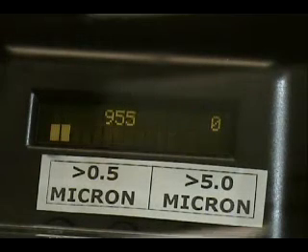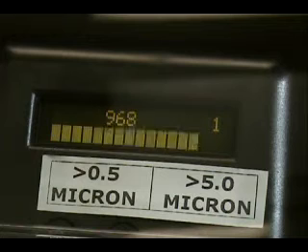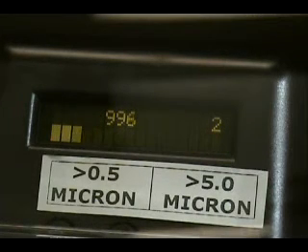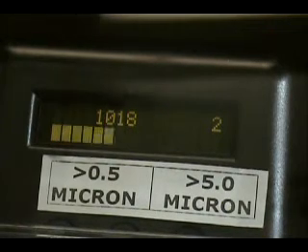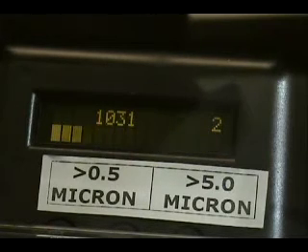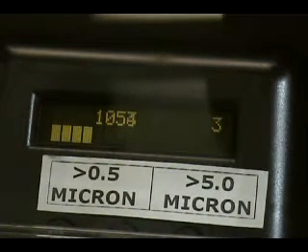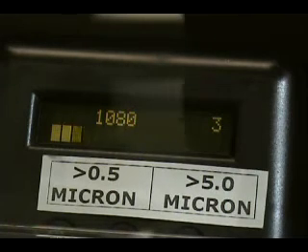I'll take the filter out — particle count will go back up. This is a clean 20 by 20, one-inch air filter. Particle count is going up. The question is, this filter was left in for a month and could have stayed in another month. Has the particle count or the static pressure — the energy used to move air — changed that much? Let's find out. We're back up to about 1054. That's about 10%, and a new filter has about 12% efficiency at half micron.